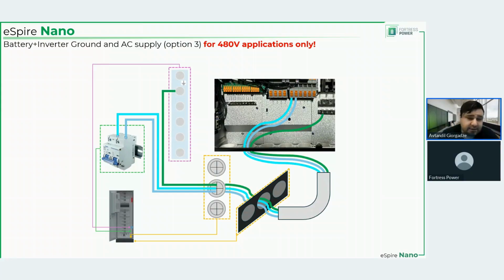Now, what do we do if we want to deliver AC power to our battery unit, the auxiliary AC supply? There will be different applications for this product, right? And depending on which application you go for, that's what you're going to have to use. So the breaker obviously will receive only one phase, and that phase will be around 277 volts because this is for 480 volt applications only.